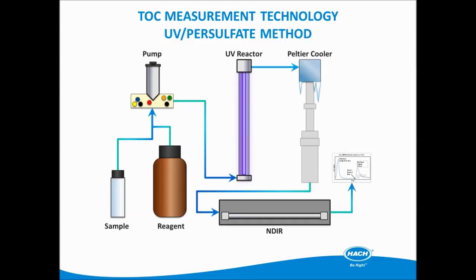Once the UV lamp turns on, the organic carbons are then oxidized. The CO2 gas is then carried through the system with a carrier gas, or CO2-free gas, to the NDIR where the CO2 is measured and results are then reported.